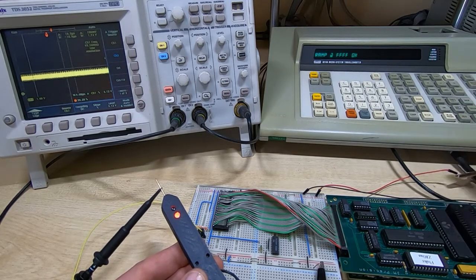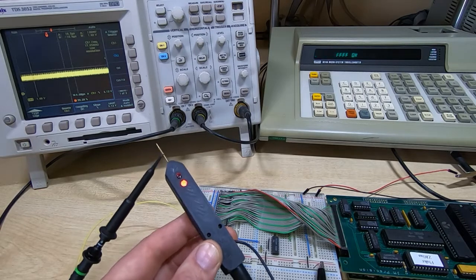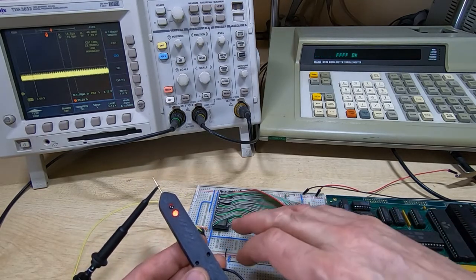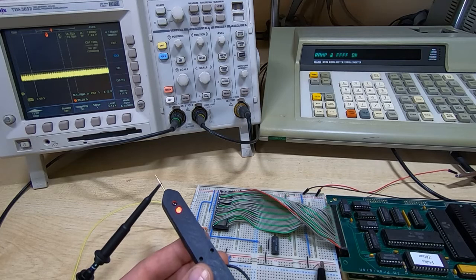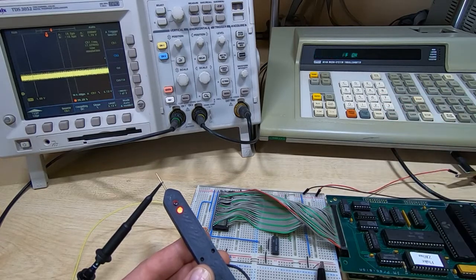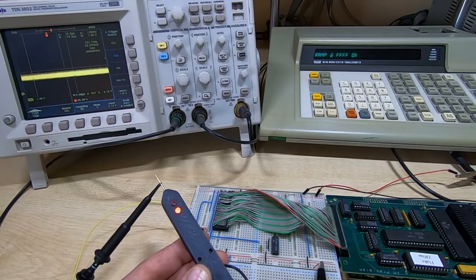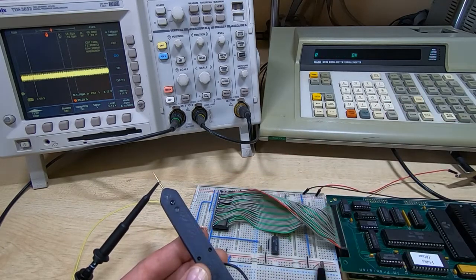Now, the other thing to bear in mind with the Fluke when you're reading the probe is it does not differentiate between a stimulus it is generating itself and stimulus on the unit under test. So, for example, if you have the Fluke providing stimulus output, then it will read that as part of its input. That's just one thing to bear in mind. If you do want to read data from the unit under test, then really you need to turn off the stimulus from the probe itself.